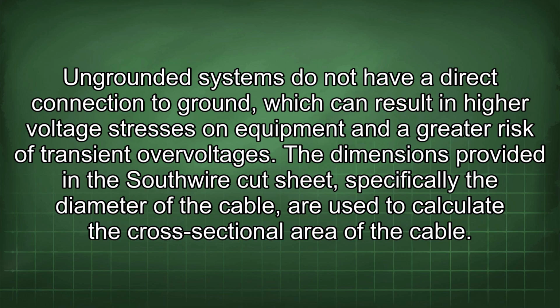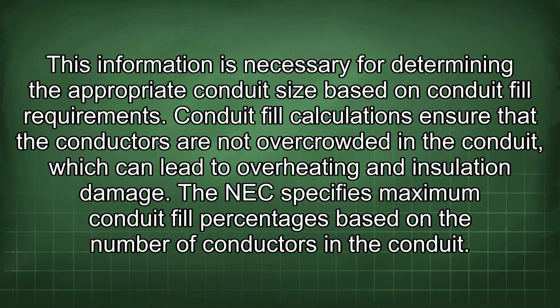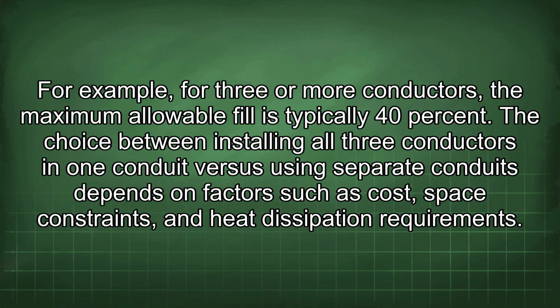The dimensions provided in the cable cut sheet, specifically the diameter of the cable, are used to calculate the cross-sectional area of the cable. This information is necessary for determining the appropriate conduit size based on conduit fill requirements. Conduit fill calculations ensure that the conductors are not overcrowded in the conduit, which can lead to overheating and insulation damage. The NEC specifies maximum conduit fill percentages based on the number of conductors in the conduit. For example, for 3 or more conductors, the maximum allowable fill is typically 40%.